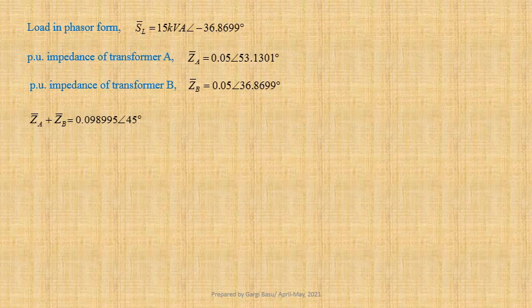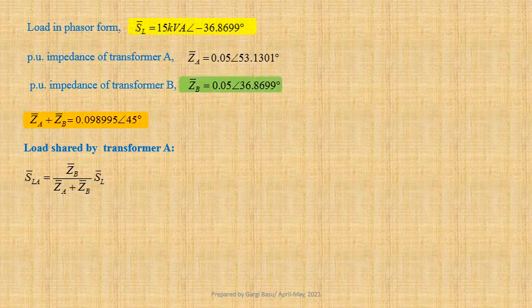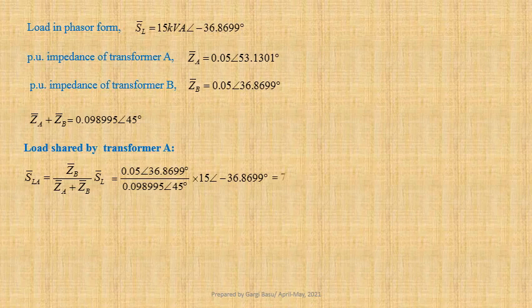Let us now determine load shared by transformer A. SLA equals ZB divided by ZA plus ZB into SL. Using values we get 0.05 at an angle 36.8699 degree divided by 0.098995 at an angle 45 degree into 15 at an angle minus 36.8699 degree. That gives us 7.5761 kilovolt ampere at an angle minus 45 degree.